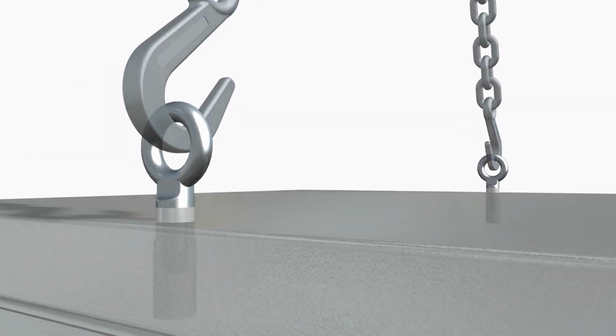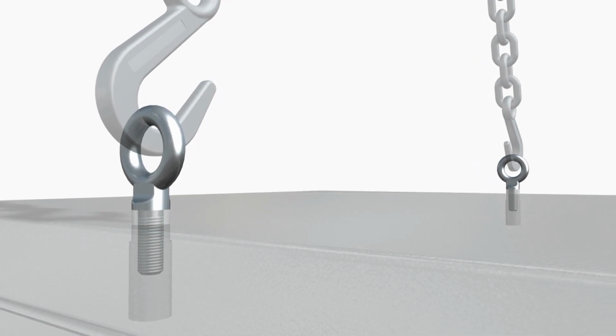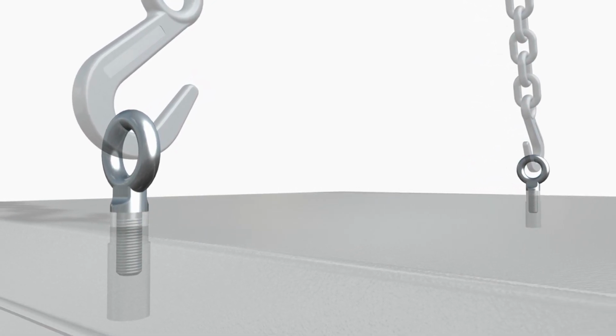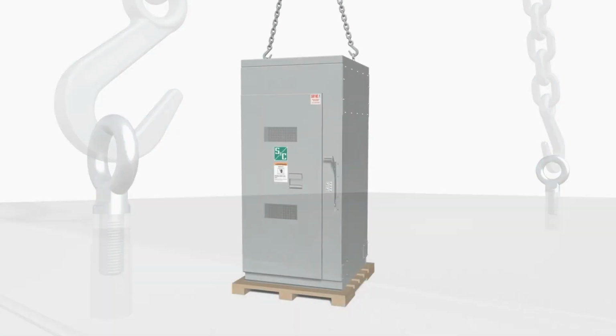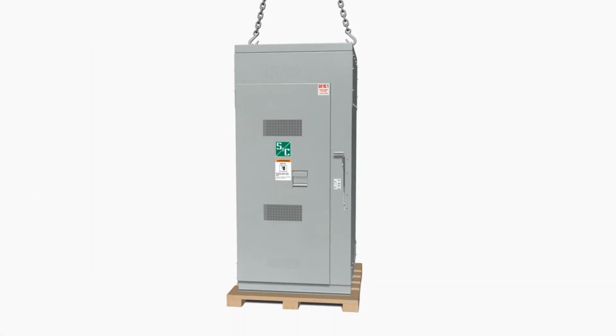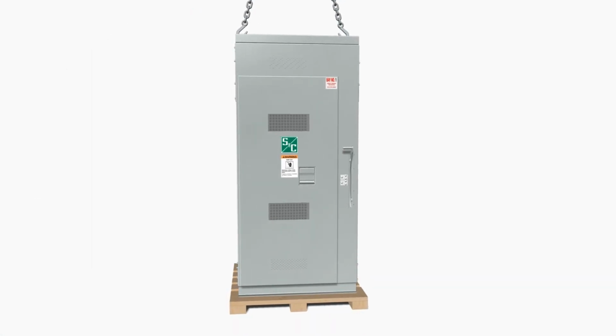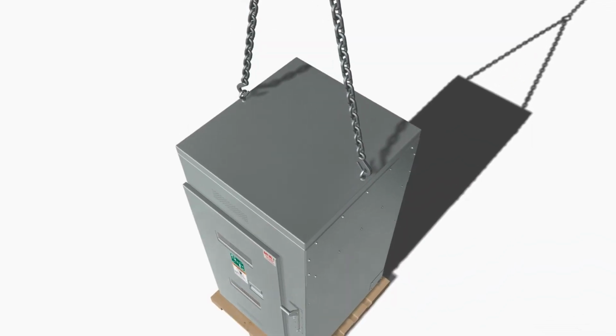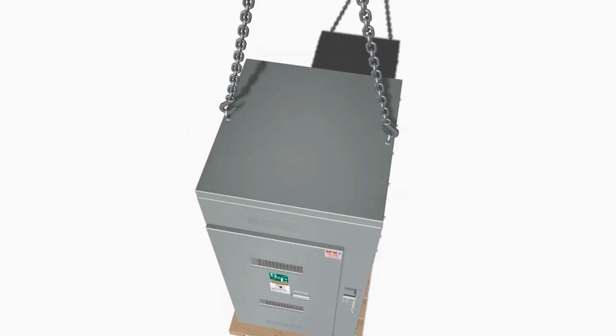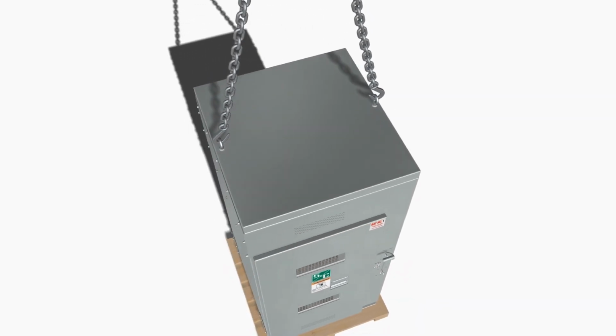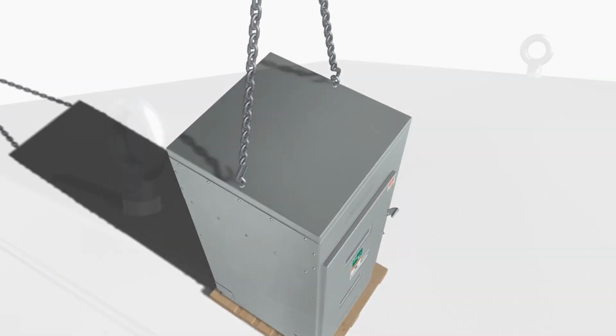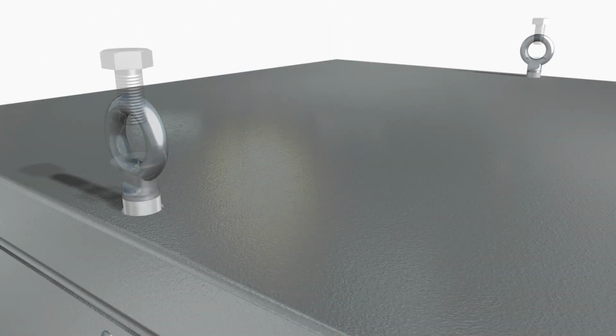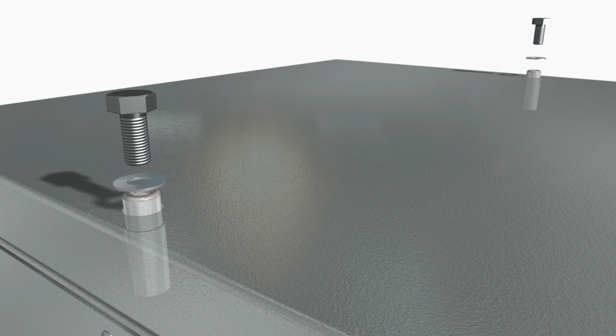Step 4. Be sure the eye bolts are screwed down to the shoulder before lifting the gear. Step 5. Avoid sudden starts and stops. It is not necessary to remove the eye bolts after the switchgear has been installed. If the eye bolts are removed, however, the holes must be plugged using galvanized bolts and washers and sealing mastic.